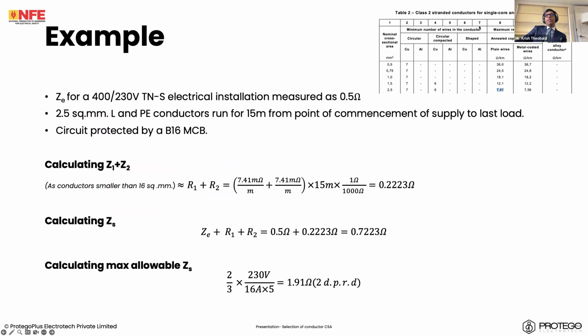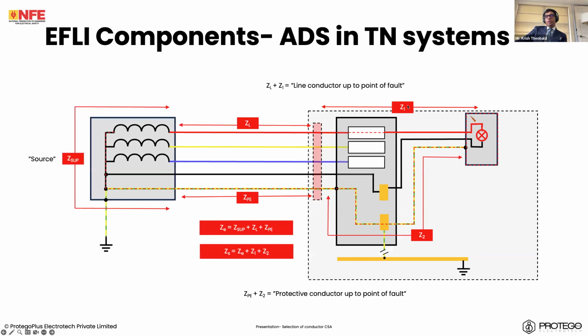Okay. I look at IEC 60228, in India IS 8130. I know for a 2.5 square mm copper conductor, it will have a resistance of 7.41 milliohms per meter. I have a line and a protective earth, so R1 plus R2: 7.41 milliohms per meter plus 7.41 milliohms per meter, multiplied by 15 meters, and I'm just correcting, sorry, milliohms, so 1 ohm per 1000 milliohms, we get 0.2223 ohms. That is the value of basically Z1 plus Z2.